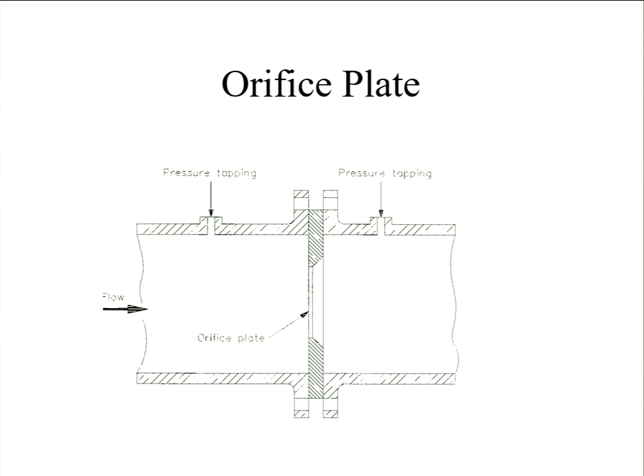What is the material specification of the orifice plate? So I think there's things like you've got to be careful about the thickness. So you've got to look at the differential pressure you're generating. What you don't want to do is inadvertently create yourself a nozzle. If you've got fast pressure changes, so if they're close coupled to compressors where you're getting rapid changes, it has to be able to withstand the forces. You can look at thickness like that.